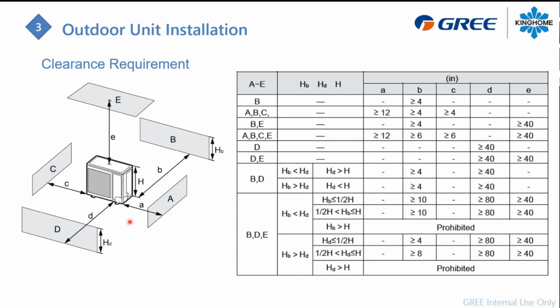Little d, in front of the unit, you will have air passing through that coil, and the outdoor fan motor will push it out. So a minimum of 40 inches in front of the unit is required, just to be sure that you will not recycle the air of the unit.